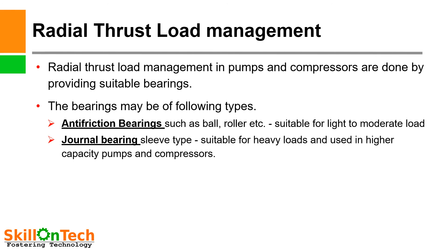Radial thrust load management in pumps and compressors is done by providing suitable bearings. The bearings may be of the following types: anti-friction bearings such as ball and roller bearings, which are suitable for light to moderate loads; and journal bearings, sleeve type, which are suitable for heavy loads and used in higher capacity pumps and compressors.